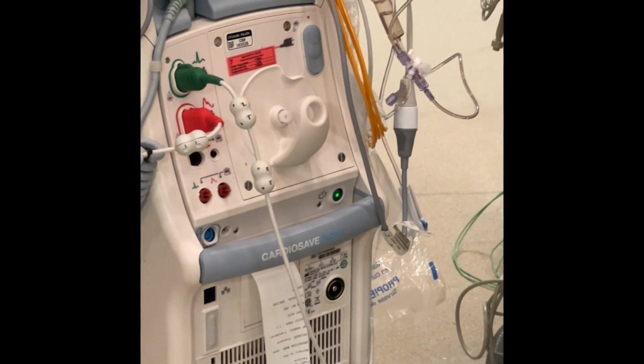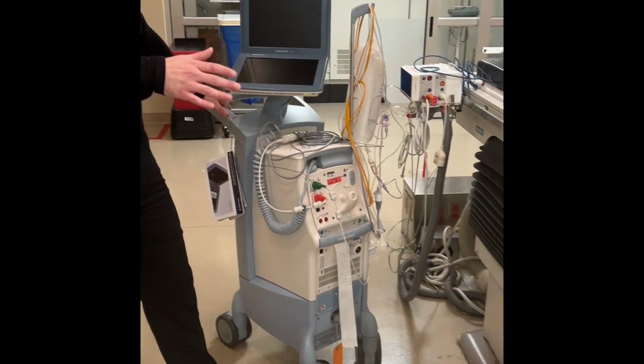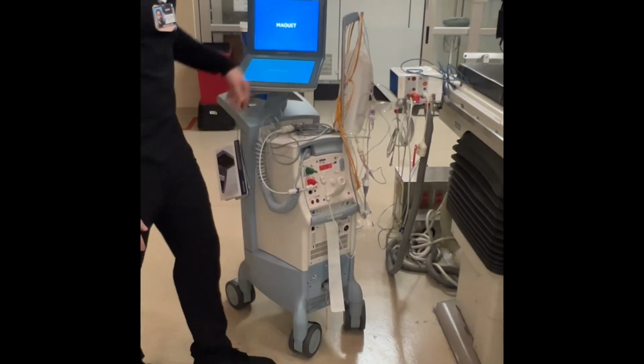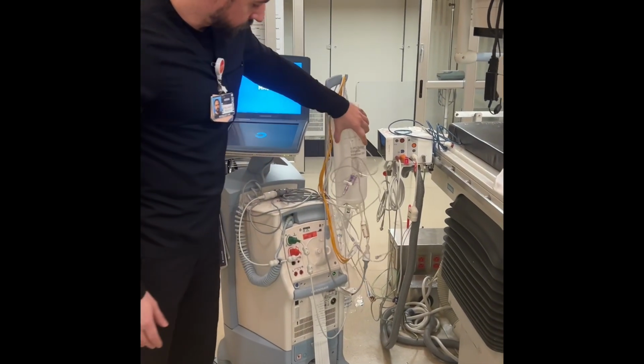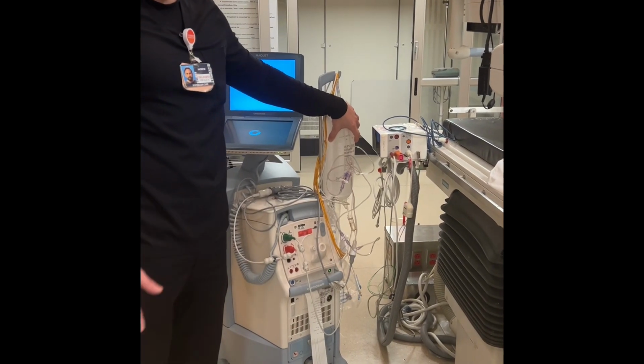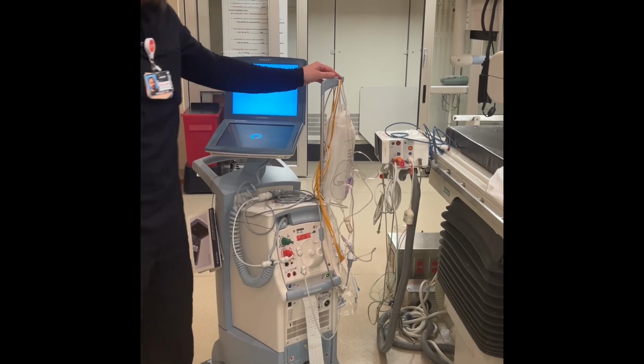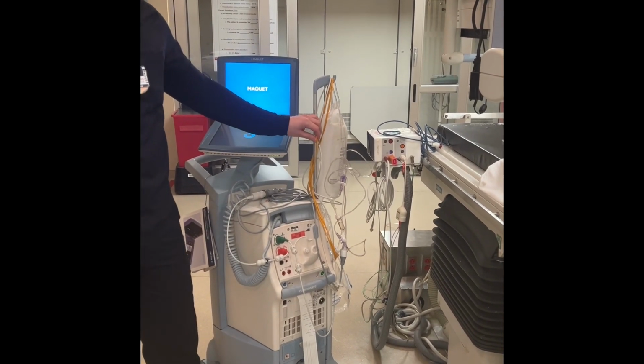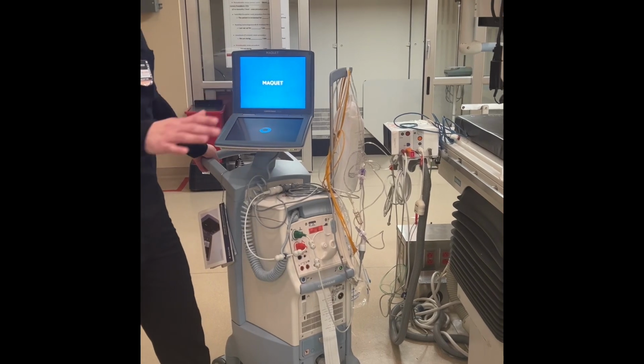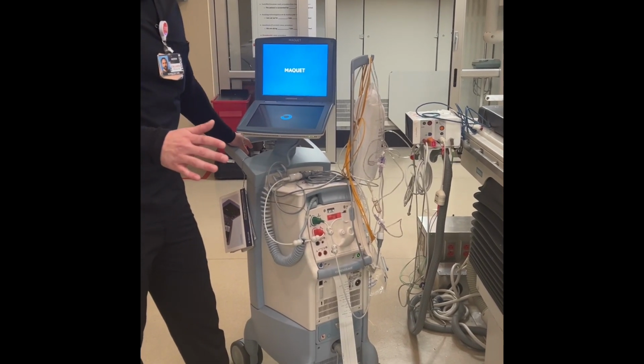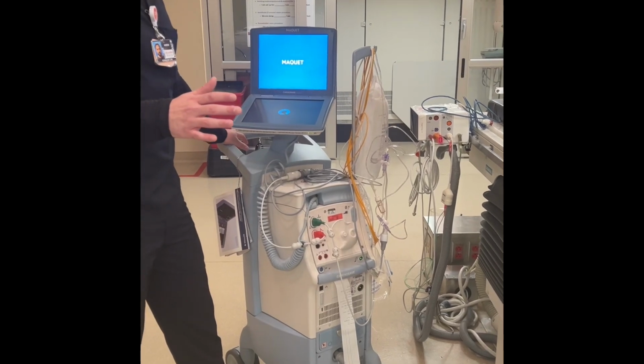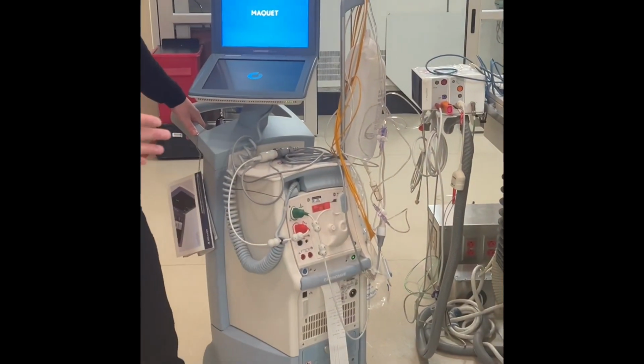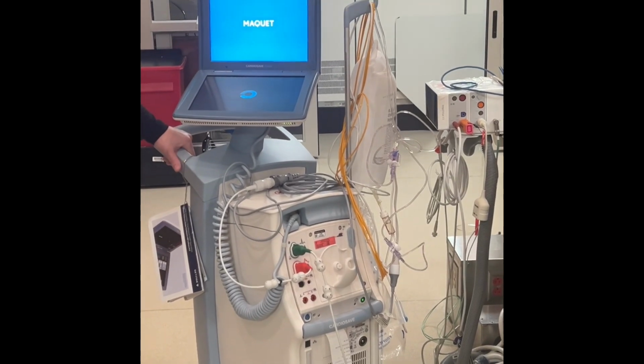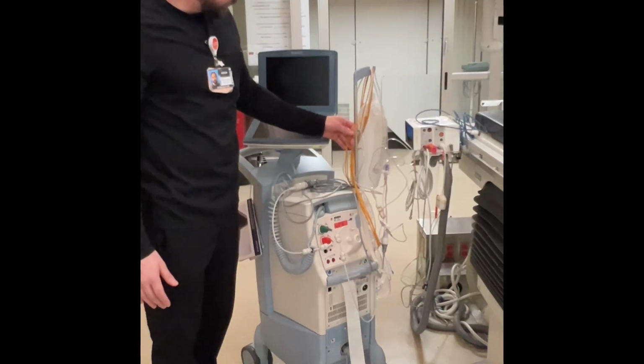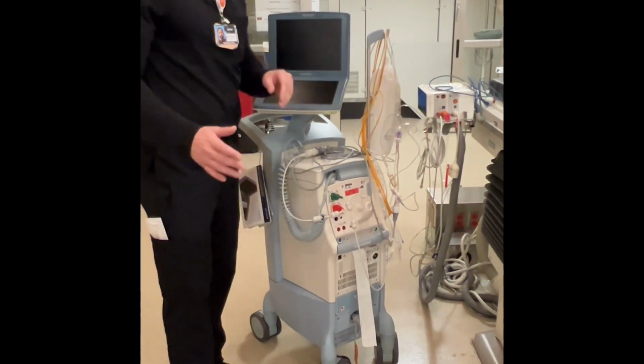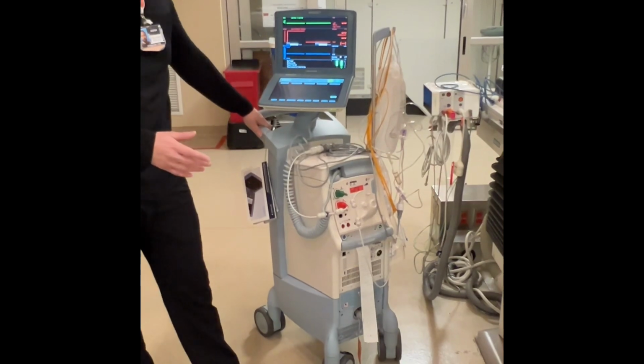You want to be kind of quick with the setup, but they do have to actually insert the balloon, so you do have some time. First thing you want to do, set up your pressure bag. Like I said, it's exactly like an A-line. And then you want to get the ECG leads on. Now, as I said, they're already working on the patient. The patient's draped. If it's a scenario in which it's more critical and maybe they're being intubated or compressions are going on, what have you, and you can't get the ECG leads on right away, that's okay. And we'll talk more about that when we touch on the triggers.